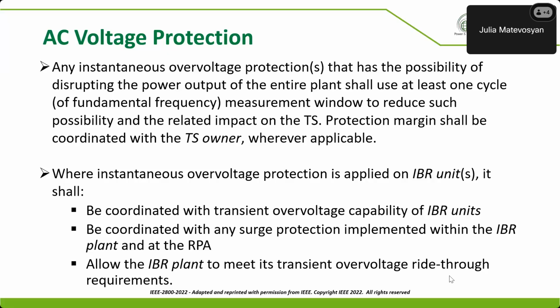from transients and whatnot. Now, the second bullet here on the screen is also fairly important. Any instantaneous voltage protection that is applied within the inverters or the wind turbine generators to protect, for example, IGBTs, needs to be coordinated with the transient overvoltage ride-through capability specified in the standard. It must also be coordinated with any surge protection that can suppress some of those transients. So we have written up some of that guidance in the standard: if it is used, it needs to be coordinated with everything else in the plant.